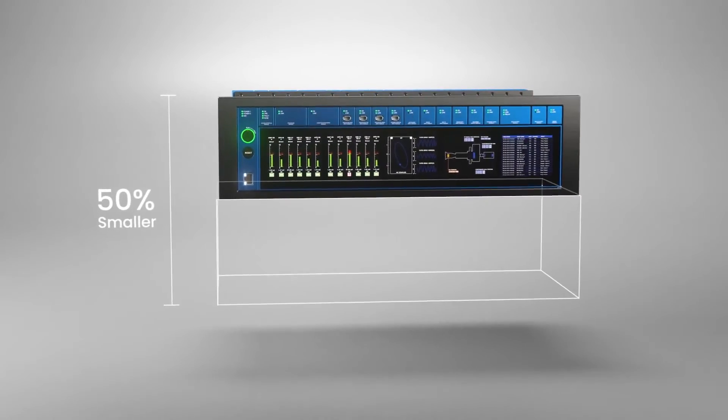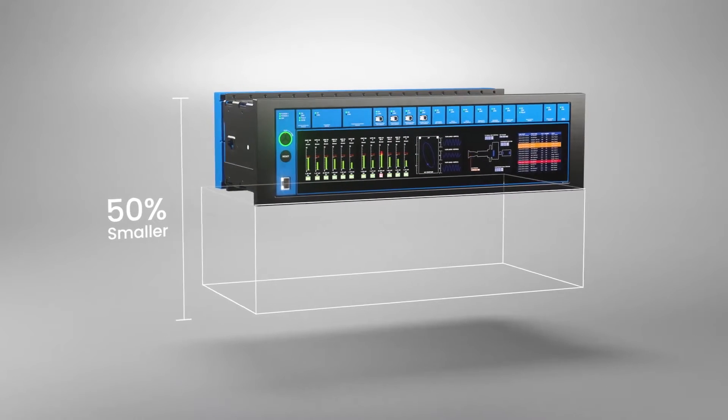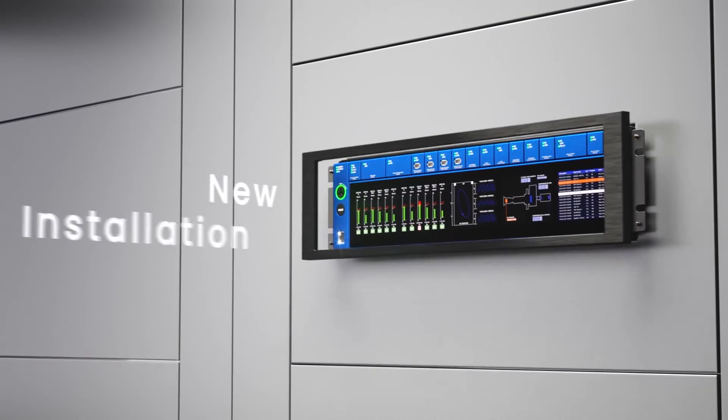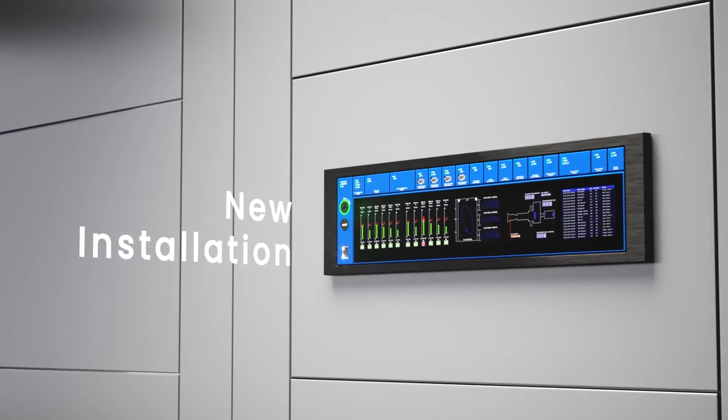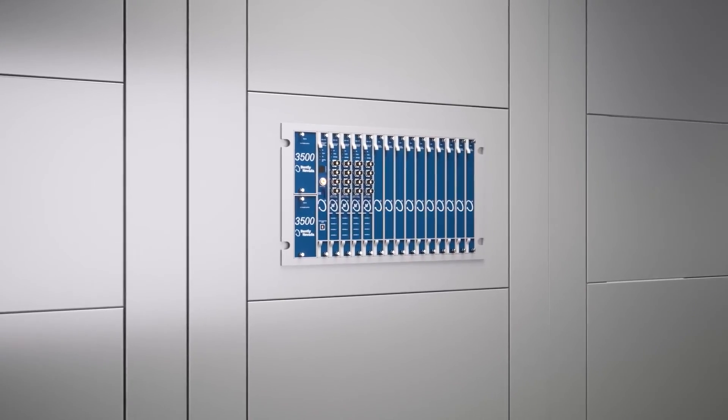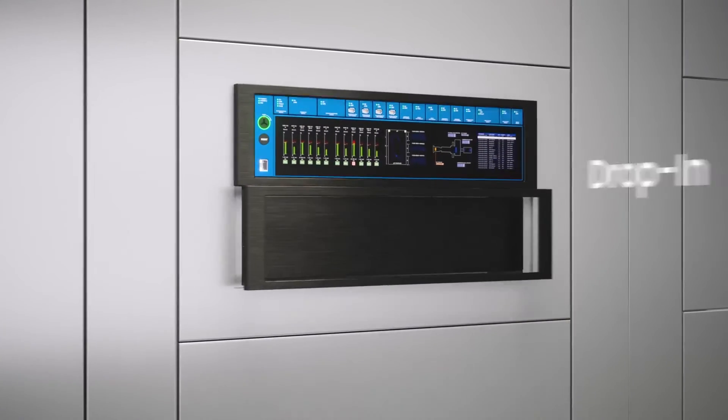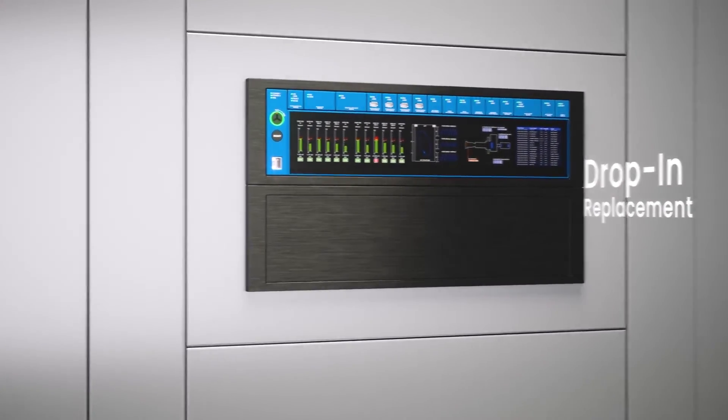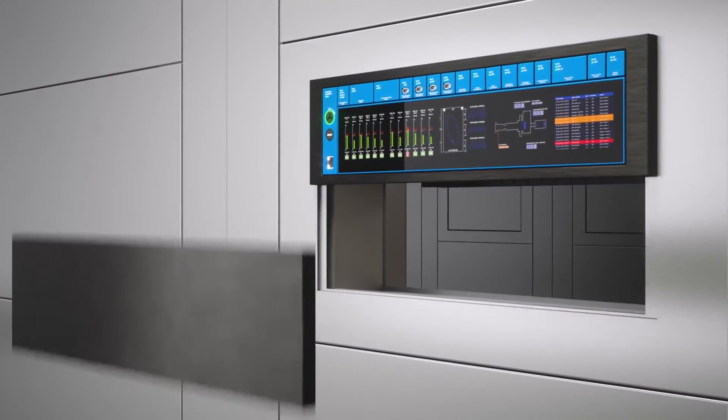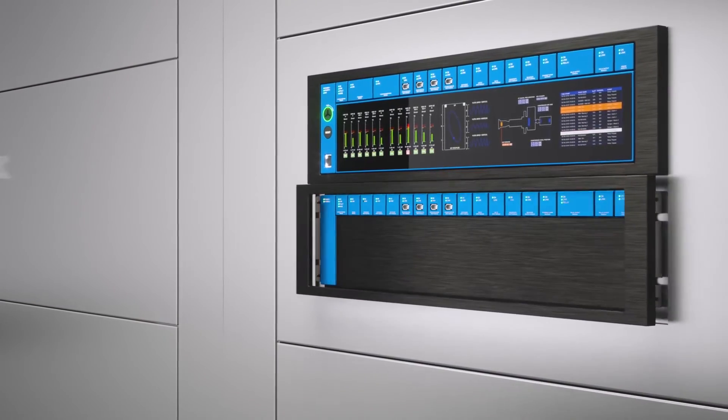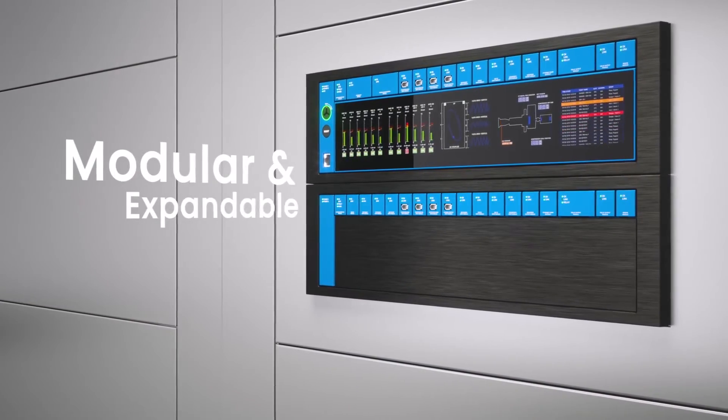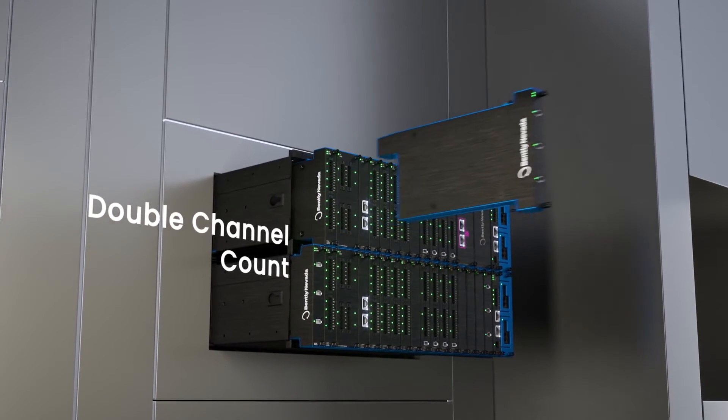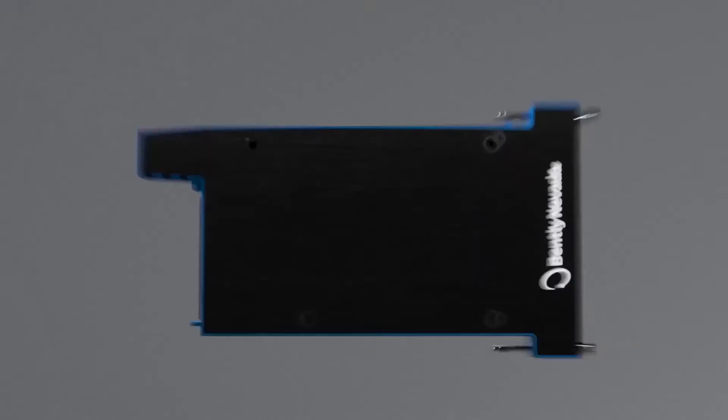Is that because these input modules can be a little bit simpler in terms of circuitry? Absolutely. They're basically taking in the inputs from the sensors from the field, simple converter in that input module, taking that data and transferring it to the backplane. All the processing heavy lifting is being done at the protection processing module.